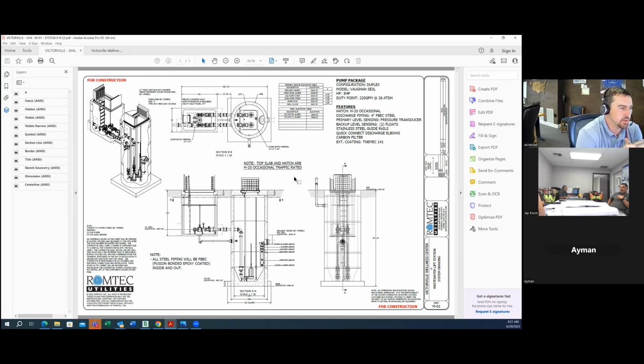For our startup, we typically allot 2 days. The first day is getting the pumps and level sensing installed and terminated in the control panel. We'll do some functionality testing, making sure things act as they're supposed to. We fill the wet well up a couple times to make sure the pumps are performing. Then the second day, we'll do cleanup, go through the punch list of small items and any programming that needs to happen. Then we'll do operation and maintenance training for the final owner or whoever needs to be trained in operating the pump station, on the second half of the second day. So startup, we allot 2 days.